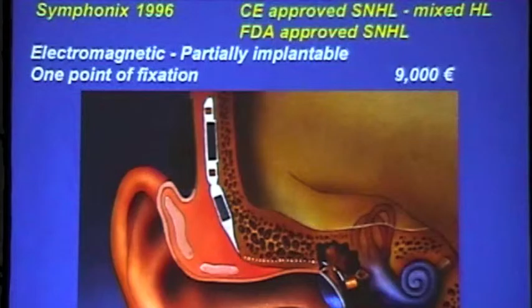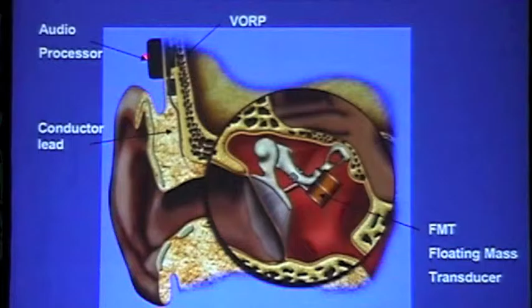It is composed of an electromagnetic vibrator which is fixed in the middle ear, an implanted receiving coil, and an external audio processor. The interest of the implant is that the magnet, in blue, is in a container between 2 elastomer balls, in red, that act like a spring, and the stimulating coil is just beside the magnet. When the magnet moves in one direction, the spring pushes it back in the opposite direction, and the spring itself pushes the titanium container. That means it is an inertial vibrator.